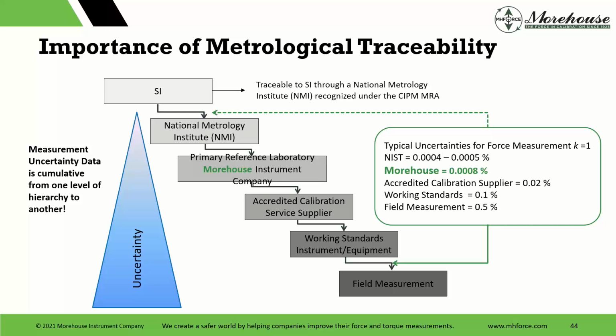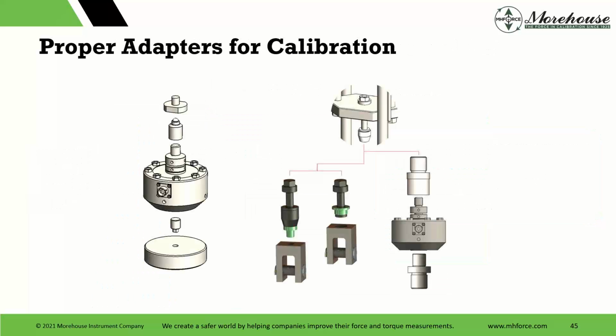But the way uncertainty works here is you have your SI, and then for most parts, you have your NMIs, your National Metrology Institutes. Then you have primary labs, and that's where we're sitting here. And then your accredited cal suppliers, working standards, field measurement. If you look at the uncertainty, it propagates, right? So if this is going to do a measurement at 4 to 5 parts per million, we can't be better than this. We have to absorb their uncertainty of the calibration. Then we add up all our uncertainties and we're at 8 parts. And we do a calibration for an accredited cal supplier. Well, they're absorbing that uncertainty. And then they're at 0.02 and working standards 0.1, and that's just how it works.